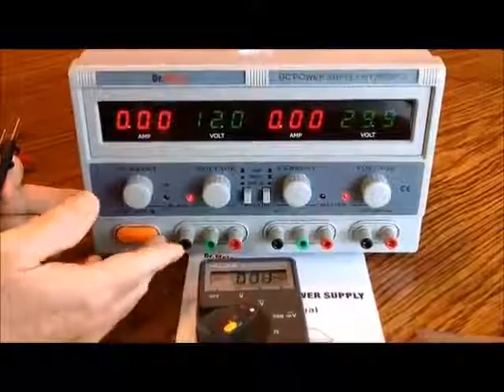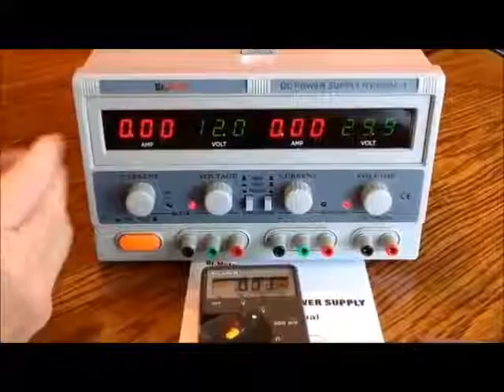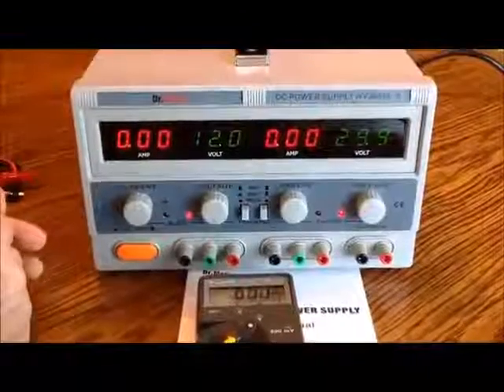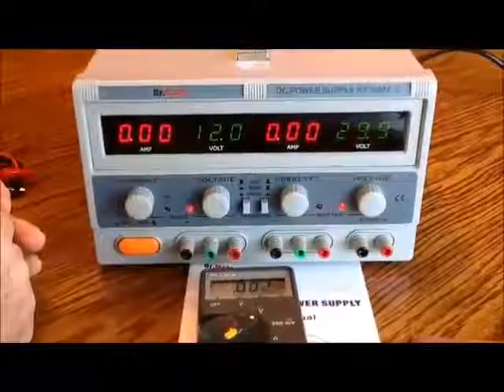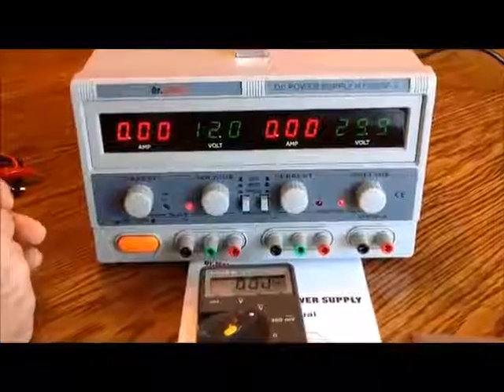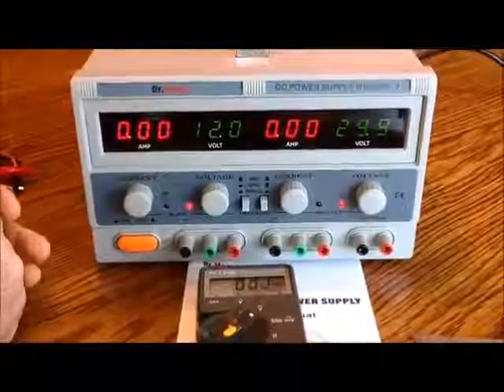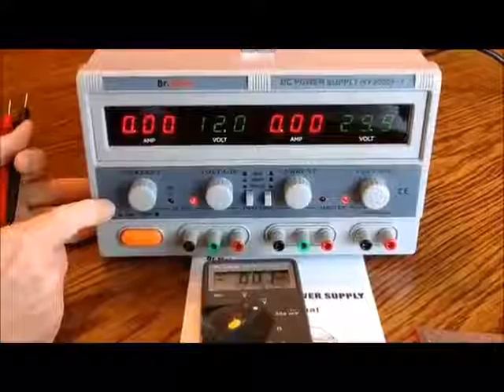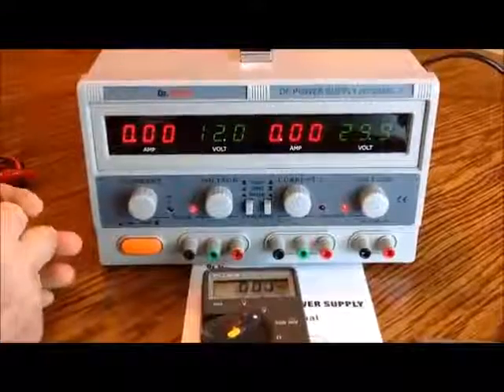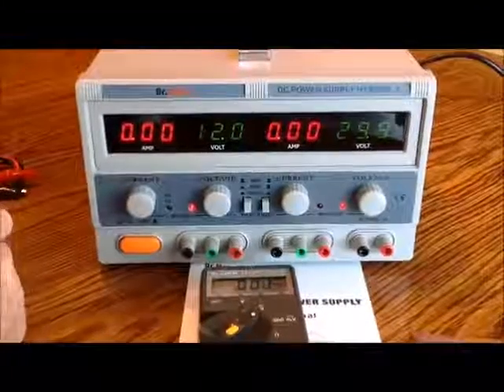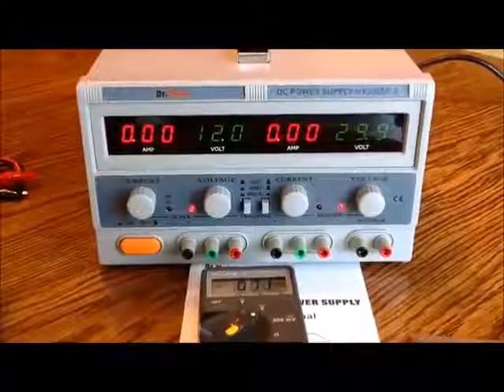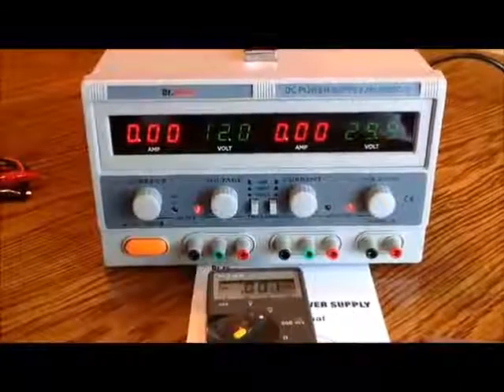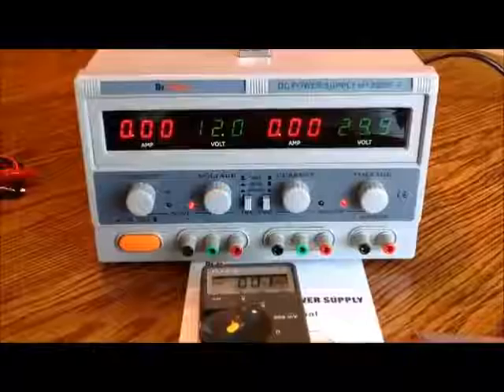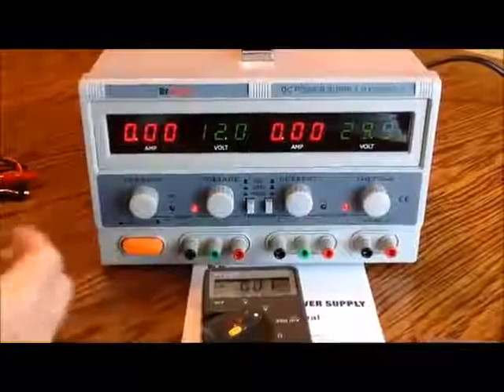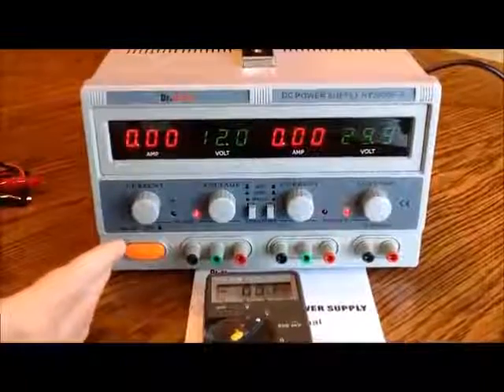Because I don't have an oscilloscope, I asked the supplier, hey, how do I know what kind of test you put this thing through? They sent me about a 40-page document including test procedures and photographs of how this unit is tested in the lab, and it's impressive. They do things like voltage regulation, harmonic current testing, high pot testing, electrostatic discharge testing to affect the outputs. It goes on and on and on.